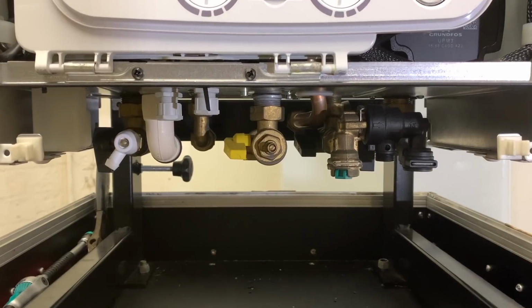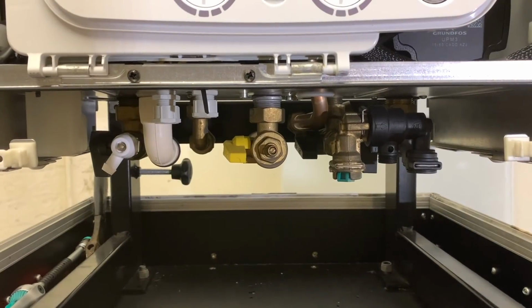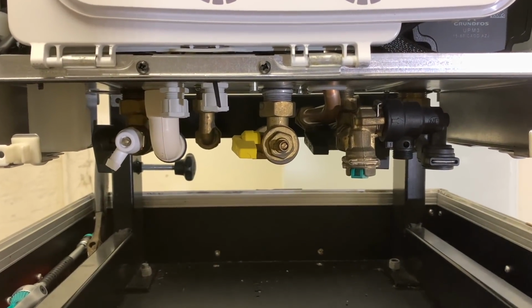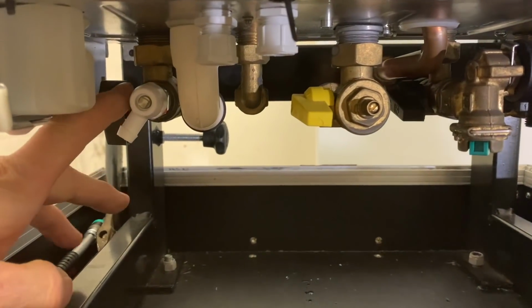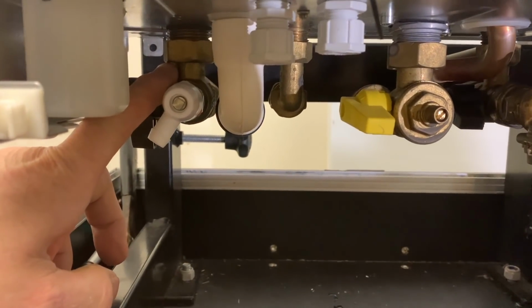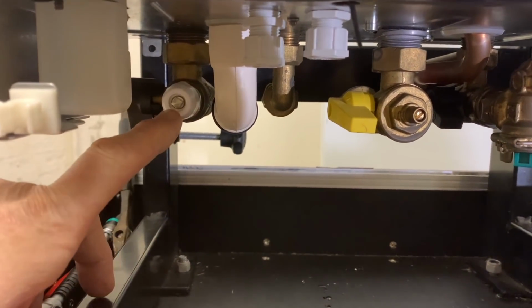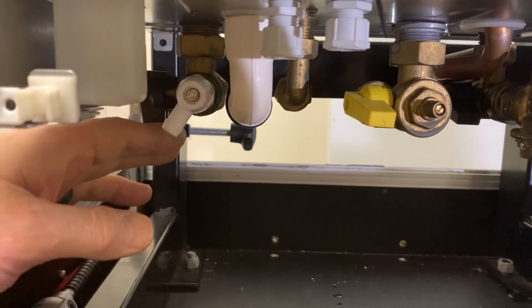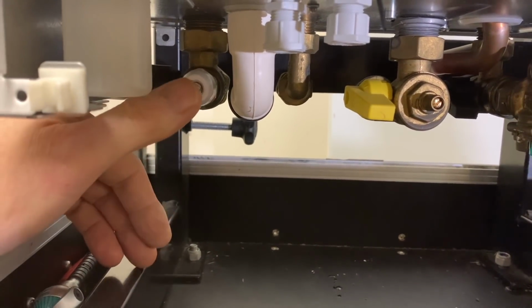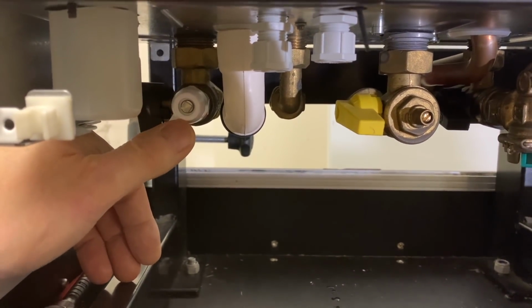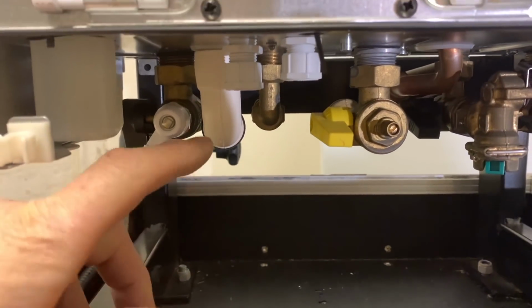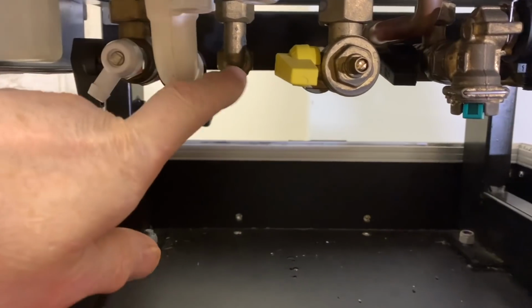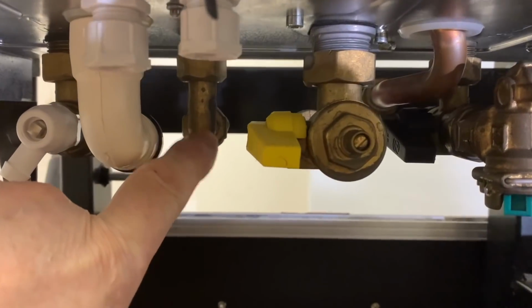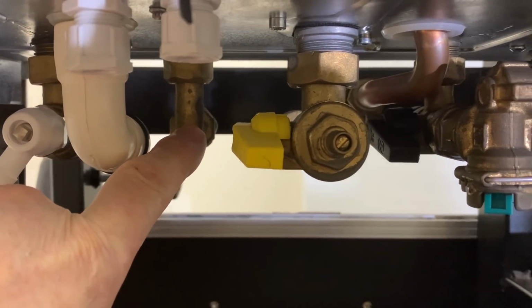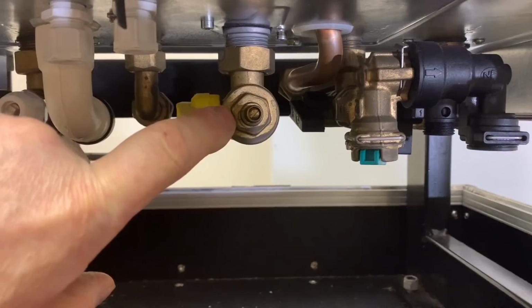Now we can see the valves underneath the actual boiler. Let's start left to right. This is our flow pipe, and this is the drain I was talking about, so you can isolate the valves here and drain the boiler without using the pressure relief valve. Then we've got the condensate, then the hot water out, then our gas connection.